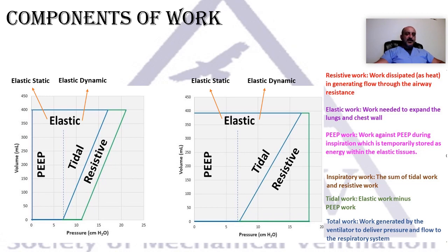As you can see, there's a difference in the shape of the pressure volume curve, and the area under the curve in pressure controlled on the right side is bigger. And we proved in a bench study that, unfortunately, pressure controlled ventilation gives higher work or power compared to volume controlled mode with the square or constant flow.